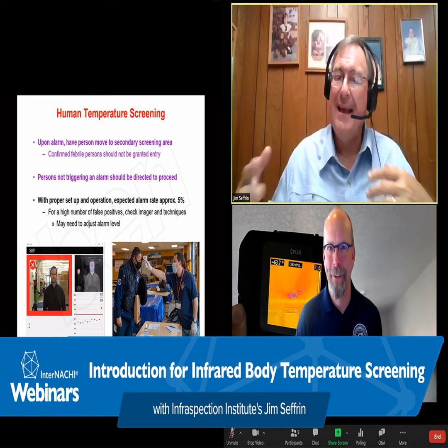Those who have a thermal imager will note that thermal imagers are extremely sensitive to small temperature differentials, or delta T's. Thermal imagers can detect delta T's as small as 1/10 of a Celsius degree, or just a fraction of a Fahrenheit degree. You see here a pair of images where a person has placed their hand on a wall surface for a few seconds and then removed it. And using a thermal imager, we can see the thermal handprint that is left behind. That handprint, whether it be on a table or on a wall, can be detectable for up to several minutes after the hand has been removed.